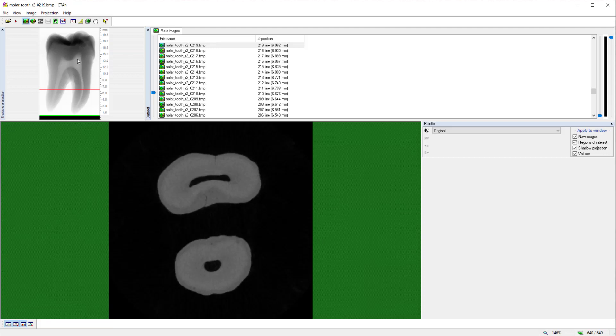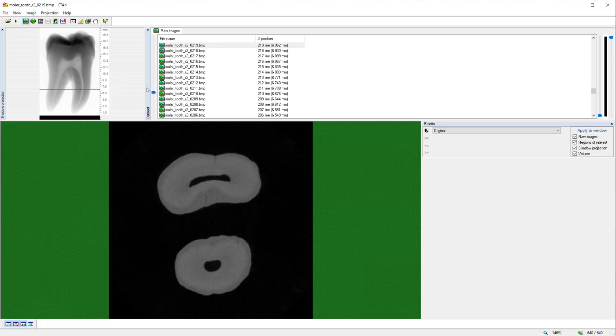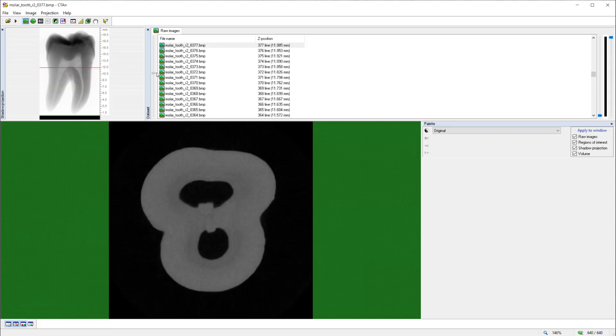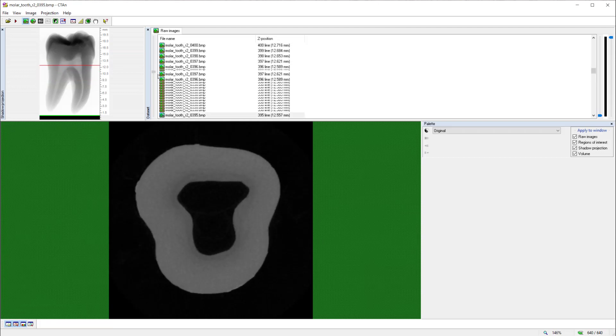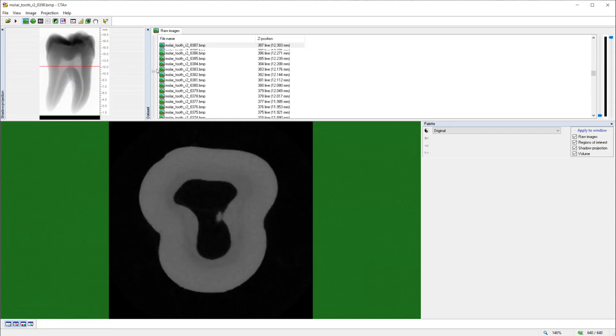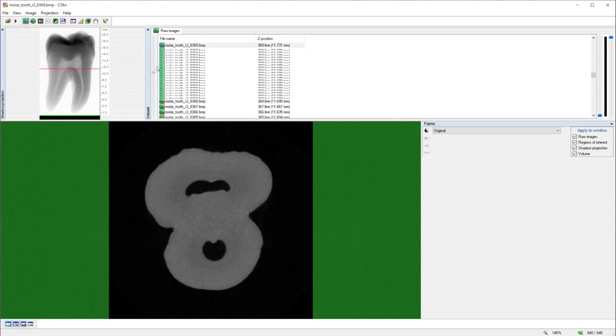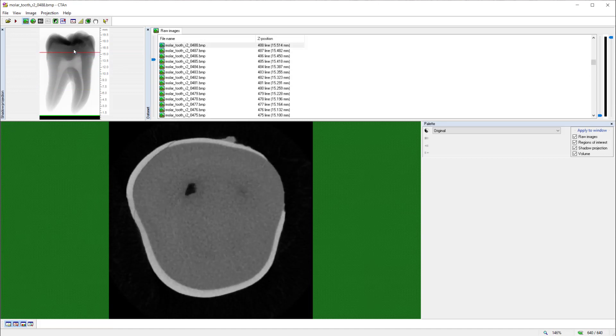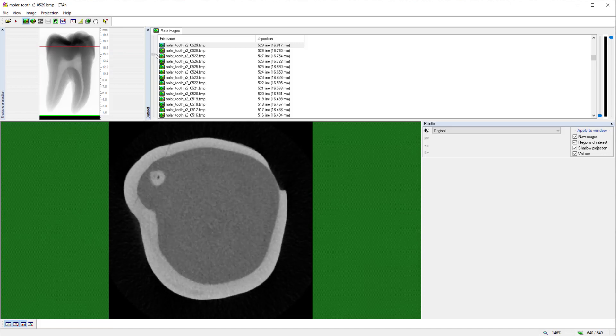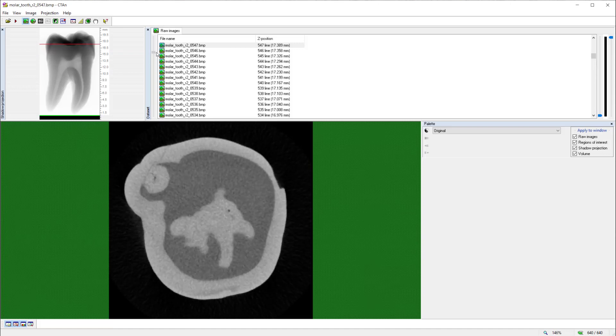In this case, the shadow projections are looking from the side at a molar tooth, whereas the cross-sections are orthogonal, or at right angles to that view, and are generating a cross-section in the plane of the red line. We can think of the red line as representing a two-dimensional plane, extending towards us and away from us. If I take the little blue slider, which is on the right-hand side of the second window, the dataset window, I can pull that slider up and down, and it changes our position. And then we can see the relationship between the shadow projection image for navigation and the cross-section slice, which is at the location of the red line.